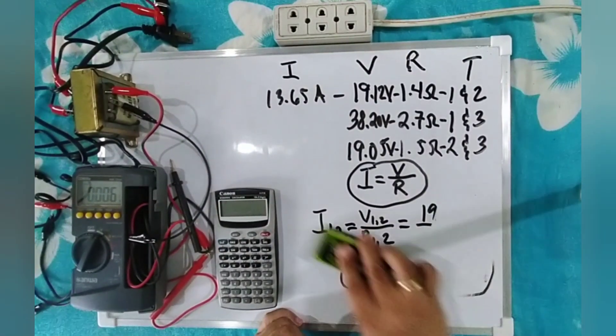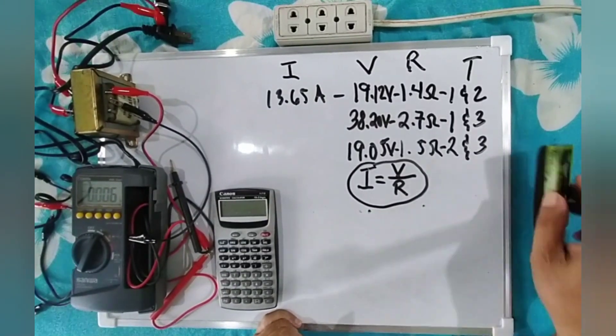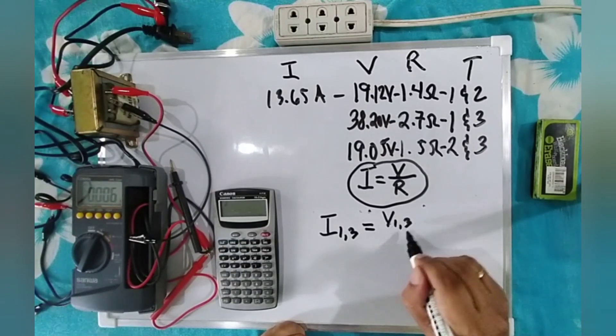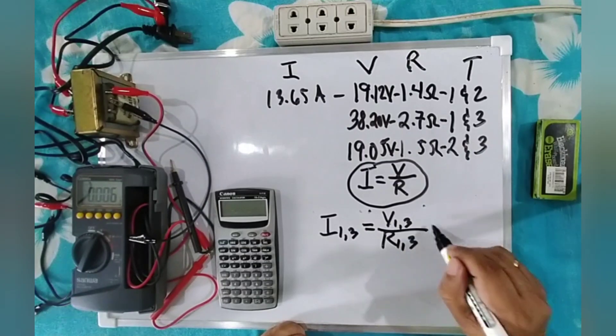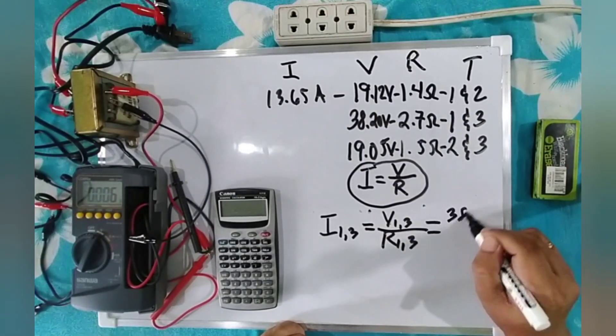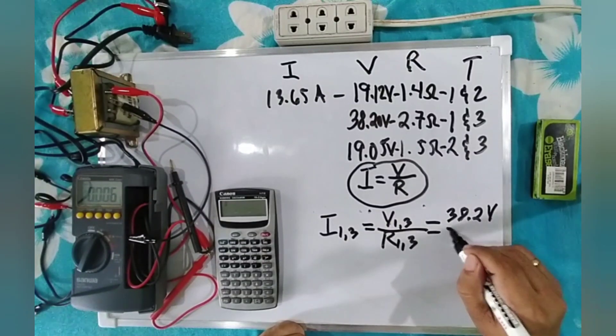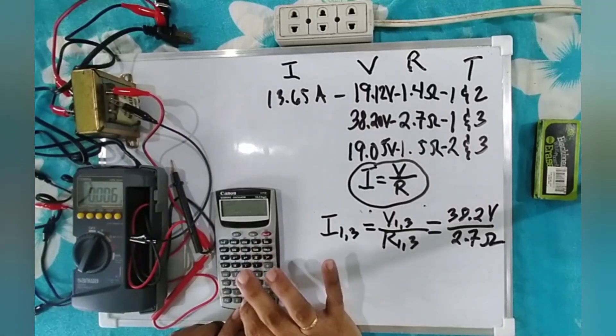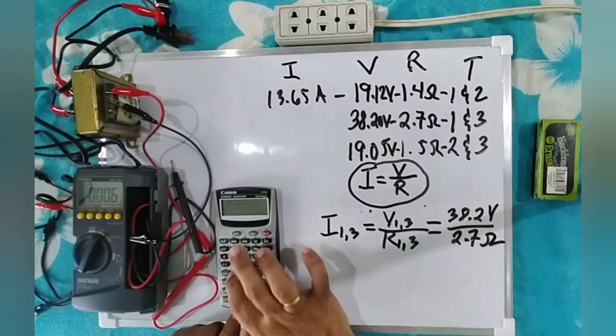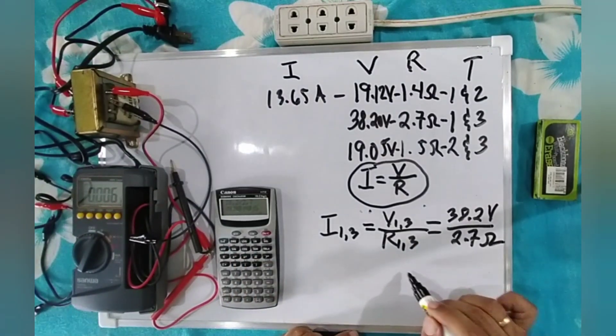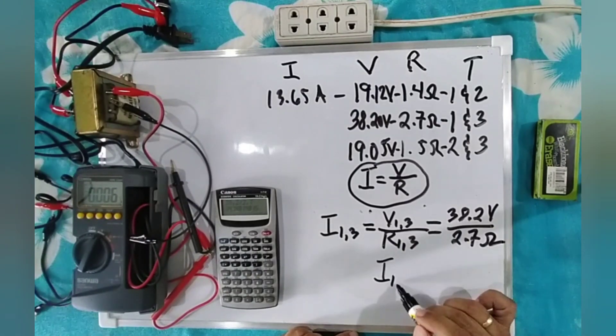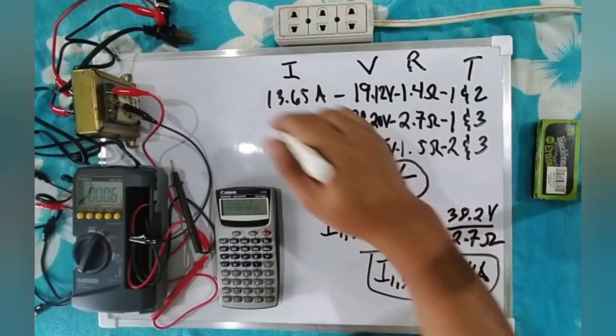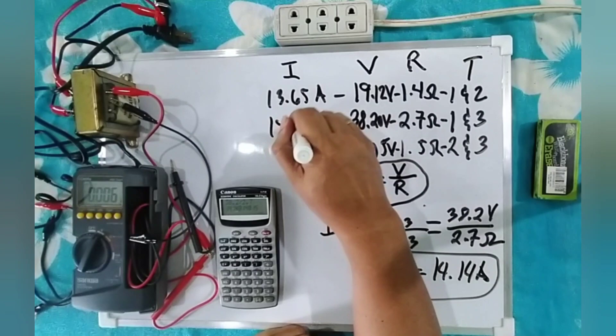Next, let's compute the no-load current of terminal one and three. Current of terminal one and three equals voltage of terminal one and three divided by resistance of terminal one and three. Substituting: 38.2 volts divided by 2.7 ohms. That equals 14.14 amperes. So the no-load current of terminal one and three is 14.14 amperes.